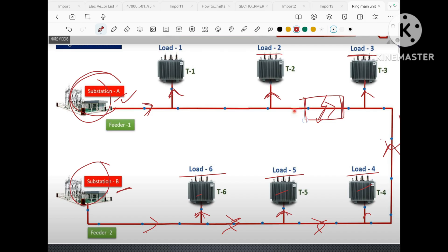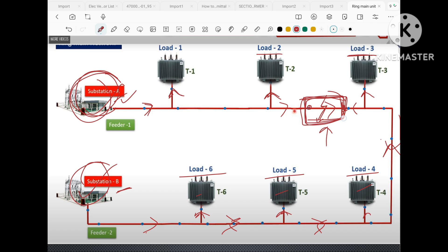Suppose this damage needs to be repaired. The ends of the damaged power cable need to be shut down. In order to shut down we have to shut down both substations, because power is reaching from each side to the fault location. Without shutting down both substations we cannot repair this cable. If we shut them down there will be a blackout in all transformers 1, 2, 3, 4, 5, 6. So this is not a reliable system even though it is connected in a ring formation.